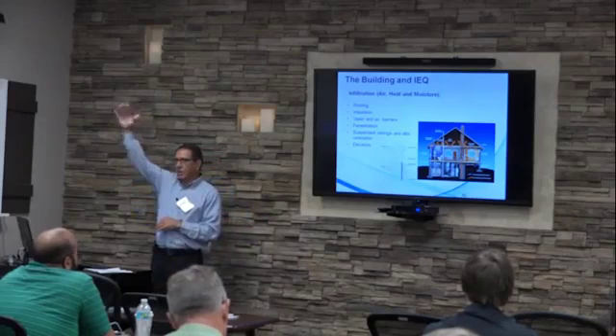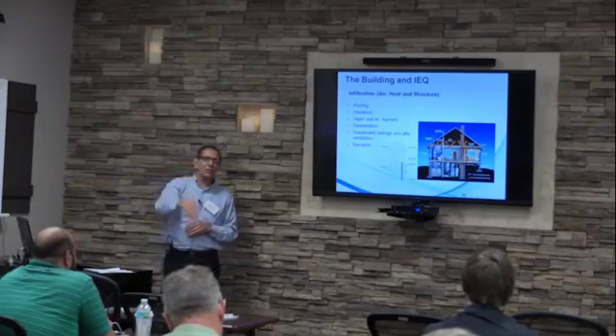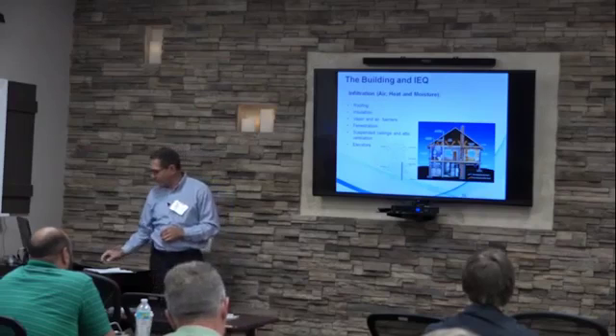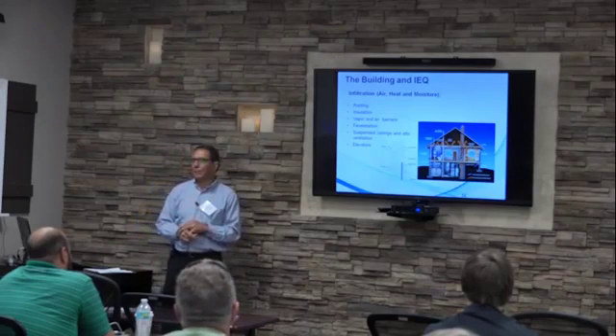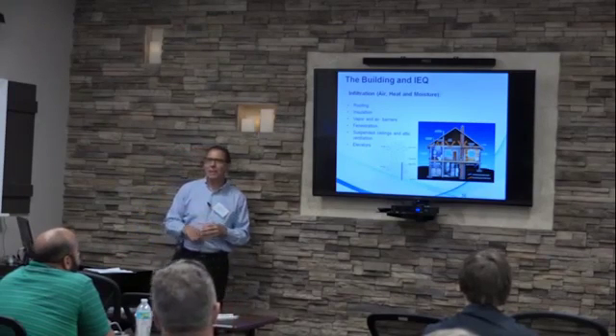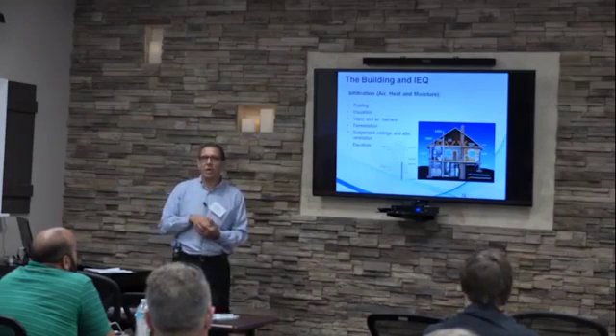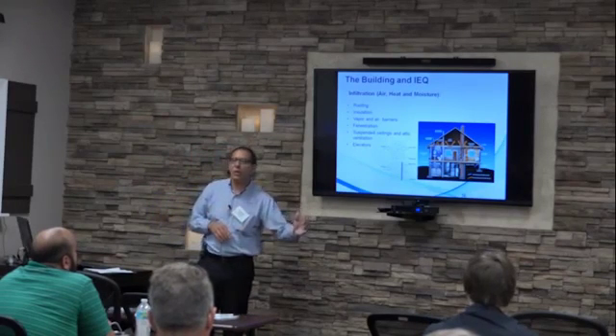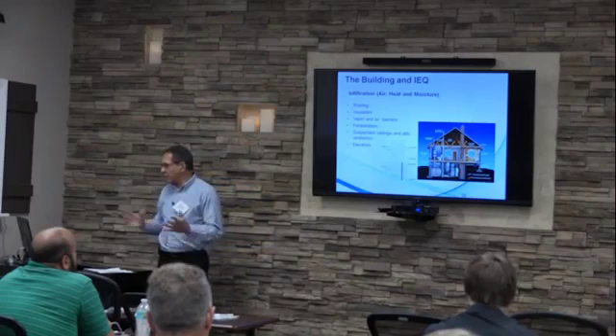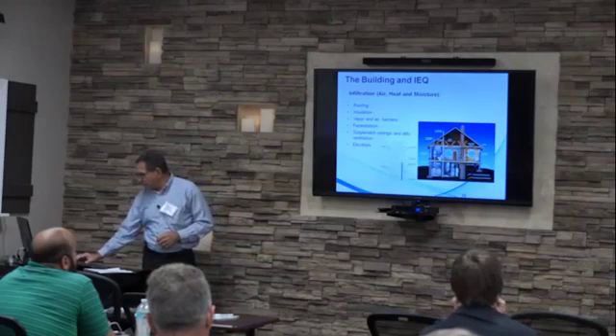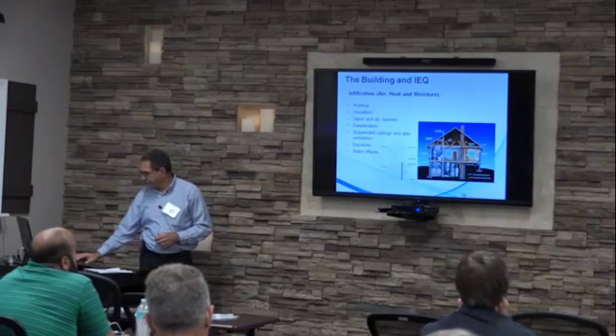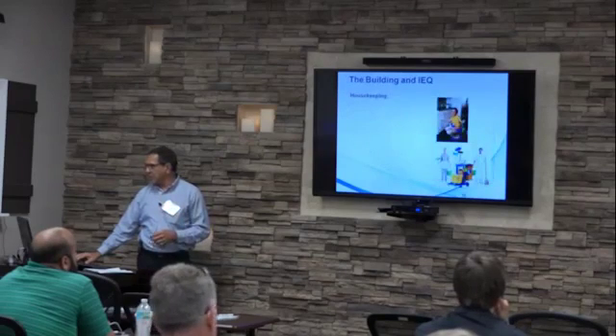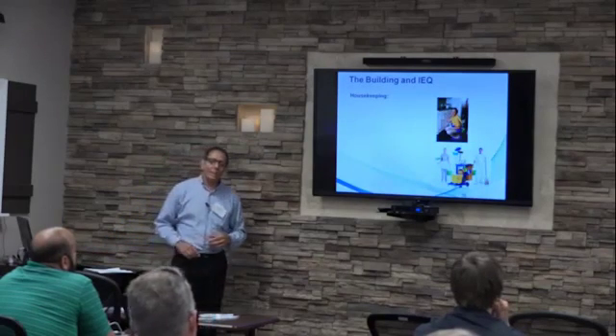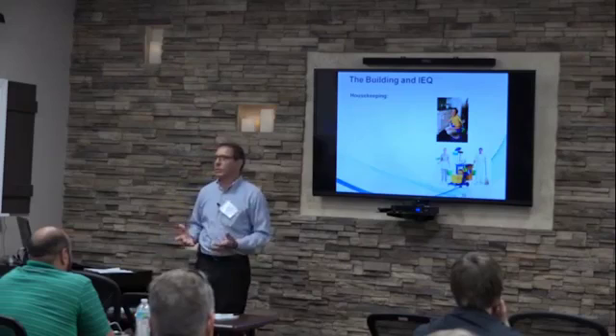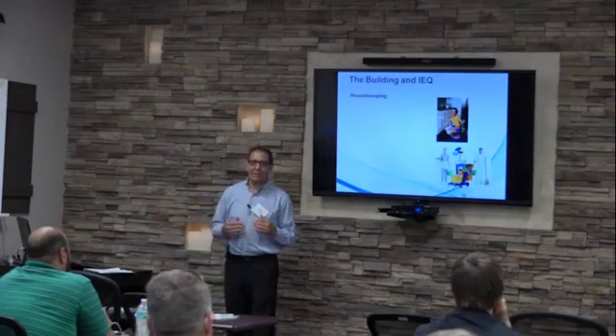And we have seen some situations where the building was not necessarily built very tight, especially above the ceiling tiles, and it allows for a great deal of infiltration. It not only brings in all the pollutants, but the humidity is also brought into the building before it passes through the cooling coils, which is an unconventional introduction of air. Stack effects are things that we need to look at.